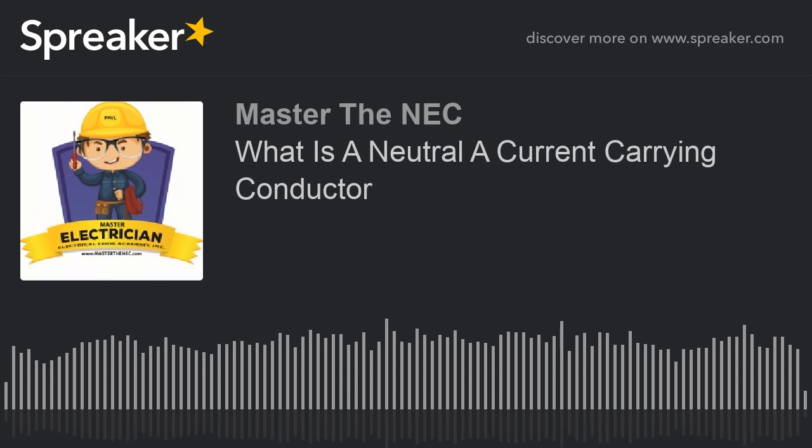And so you start burning up transformers, you start overloading neutrals. You don't take those things into consideration, then that's when you get a lot of those neutrals we see in buildings that it was a white conductor and now it looks brown. It's because they moved around these loads and they weren't real cognizant of what they were doing. They just popped them all in there, or somebody's come in there at a later date and changed things, and now you have this issue, whereas you have accumulatives, or they didn't take into account the amount of current that would be traveling, or the harmonic effects.